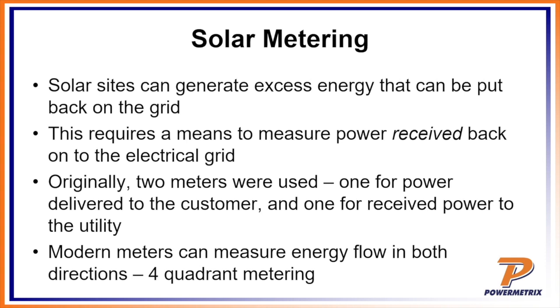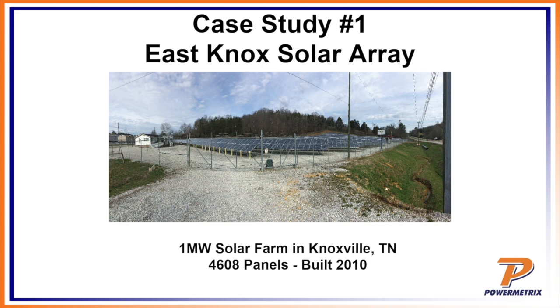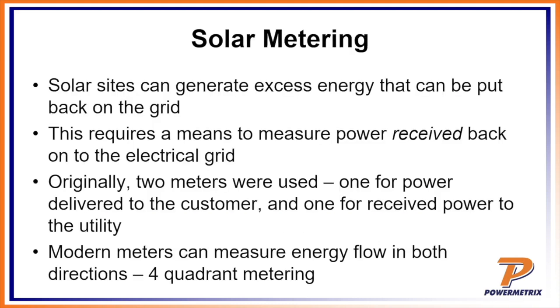So you're always measuring power received and power delivered. In the past, they used to use 2 meters, and now most of the meters are all 4-quadrant bidirectional, so there's no need to do that anymore. And that's kind of what we're assuming. What would happen if you didn't have a bidirectional meter and got out on this? If you didn't have a bidirectional meter, you would not measure any received energy.